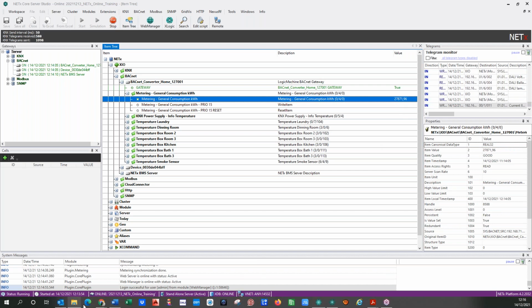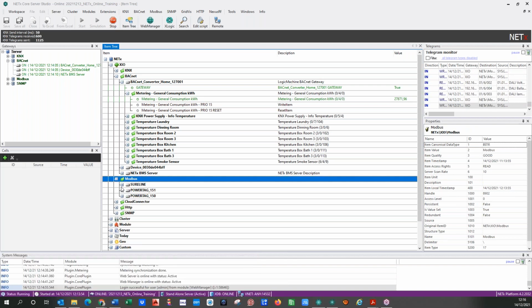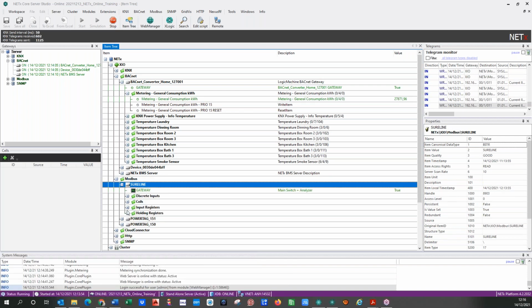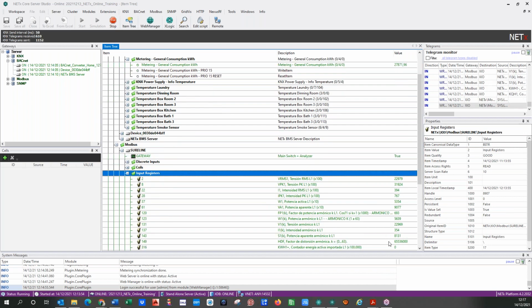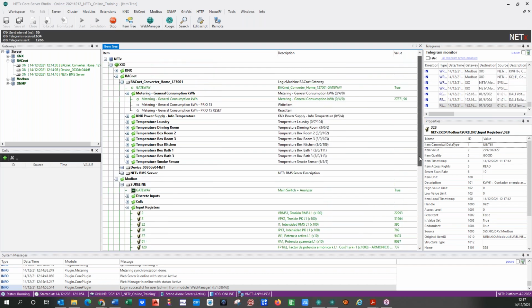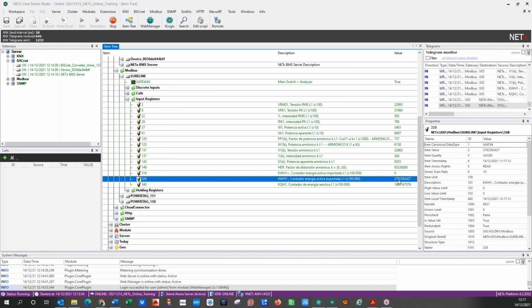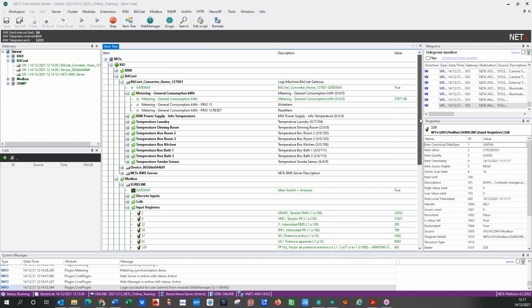So I don't need to apply scaling, because if I take it from Modbus, I have the same value, but is 100,000 times the right value. So it's, for me, it's better to get this one, 27,871, 27,923. Well, this is a bit more accurate, but it's okay.